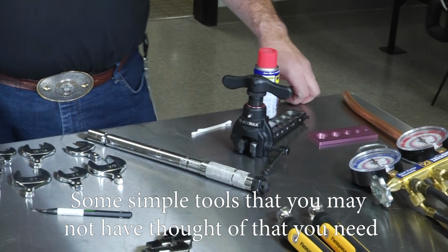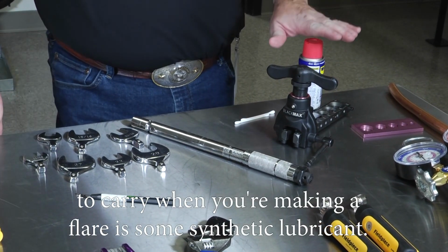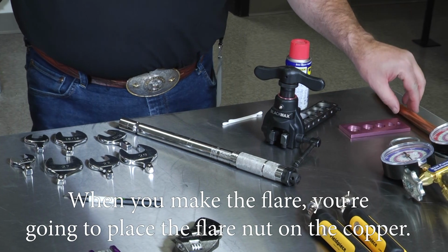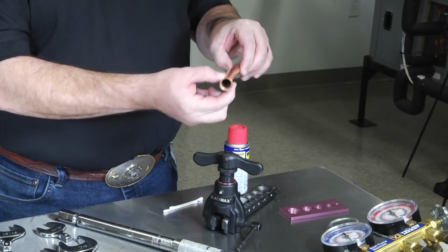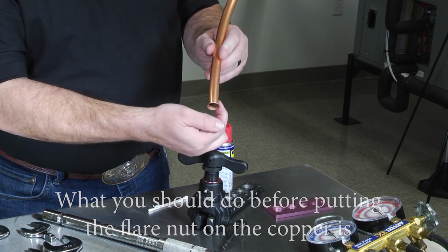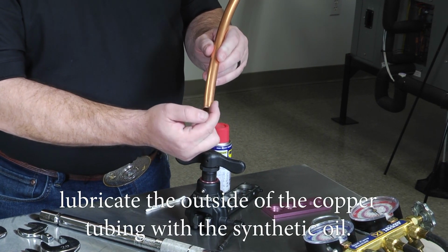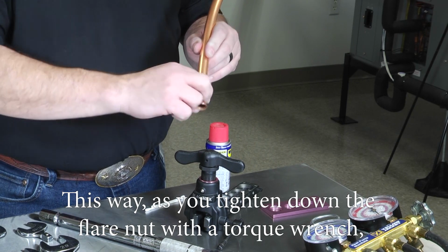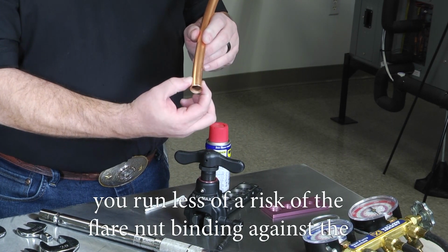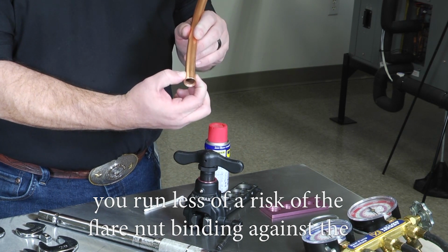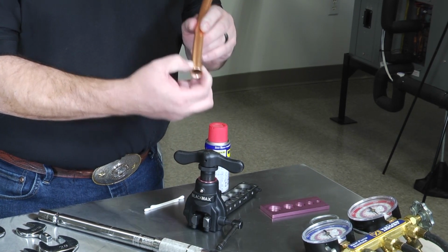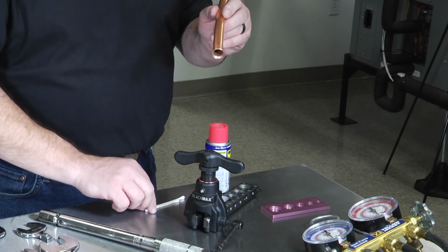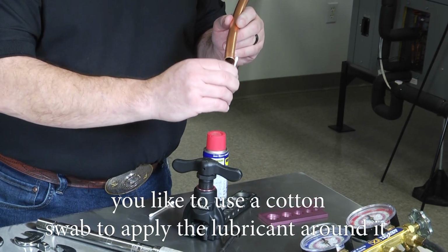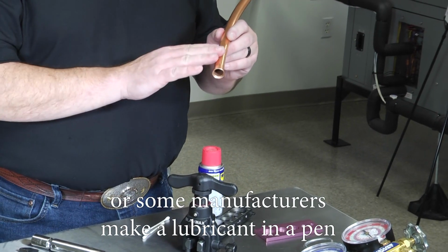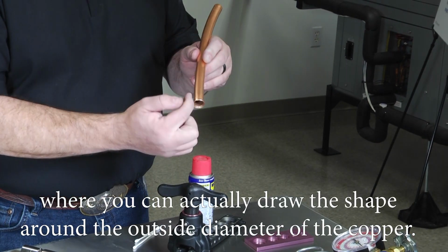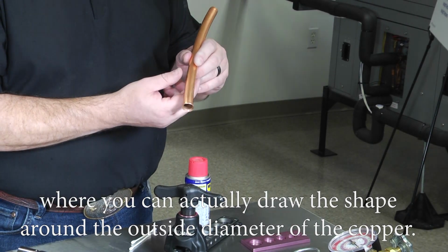Some simple tools that you may not have thought of that you need to carry when you're making a flare is some synthetic lubricant. When you make the flare, you're going to place the flare nut on the copper. What you should do before putting the flare nut on the copper is lubricate the outside of the copper tubing with the synthetic oil. This way, as you tighten down the flare nut with a torque wrench, you run less of a risk of the flare nut binding against the copper and twisting and damaging your copper. Several different ways to do it, whether you like a spray lubricant, you like to be able to use a cotton swab to apply the lubricant around it, or some manufacturers make a lubricant in a pen that you can actually draw the shape around the outside diameter of the copper.